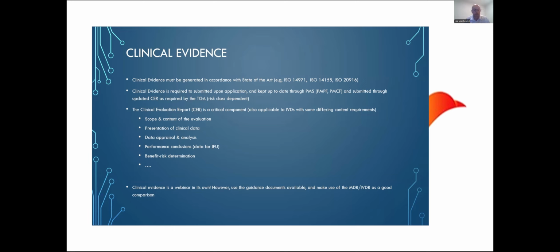The clinical evaluation report is the critical document in this regard, and there's very good guidance that the TGA provides on the content for your CER. Now, I could talk for hours on clinical evidence requirements and how to demonstrate clinical evidence, but I have very limited time today. So please use the guidance documents available. But the golden rule is the MDR and the IVDR requirements are pretty similar in terms of the amount of evidence that you need to generate.